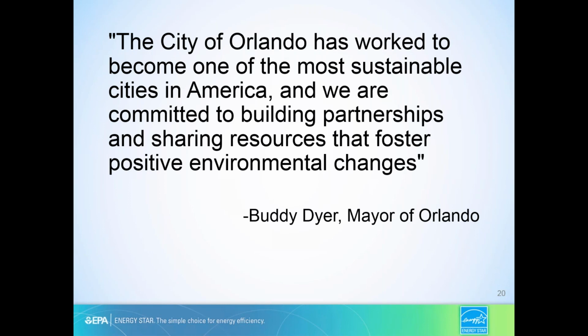One of the other things we've done is go through our community centers and fire stations to make sure they're on building automated controls or smart thermostats, so that when the population is transient—like firefighters leaving for a call for a couple hours—we're not continuing to cool the building to the desired set point until they return. It goes into a setback mode, creeping up to 74, 76, 78 degrees, but won't go above that. It won't entirely turn off until they come back and occupancy sensors detect them, and then it cranks back down to their desired set point.